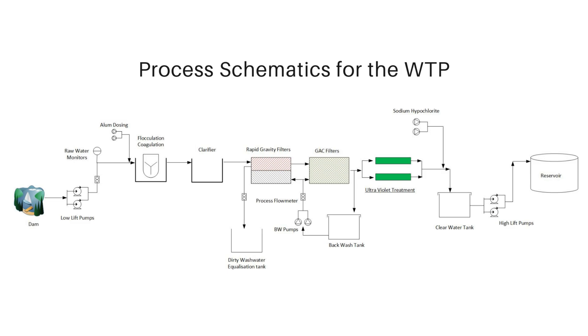Before the water enters the flocculation tanks we dose aluminium sulfate, which is a coagulant. The water then flows from the flocculation tanks to the clarifier, then it goes to the rapid gravity filters. These filters use sand as a filtration medium — we have a choice to use sand only or a dual media filter with sand and anthracite, which we will determine later during design. From the rapid gravity filters, the water is collected and goes into the GAC filters.